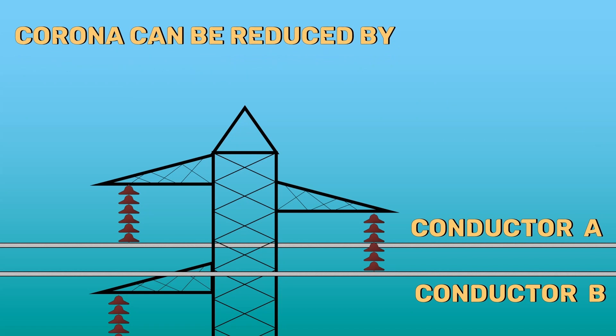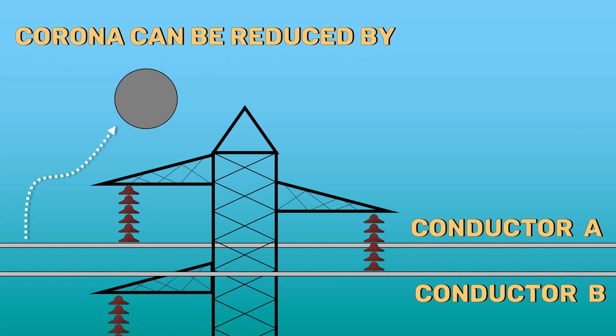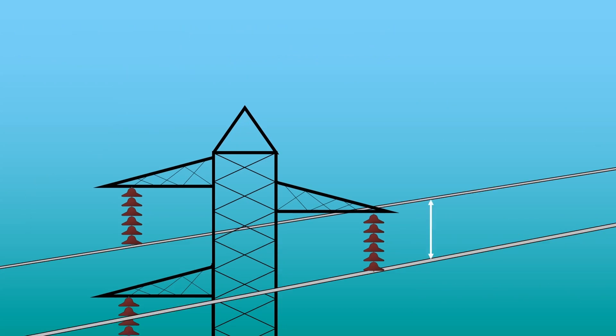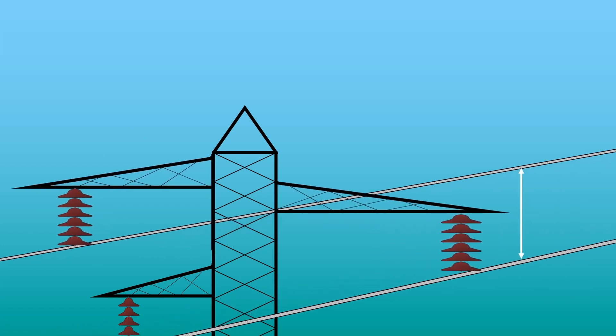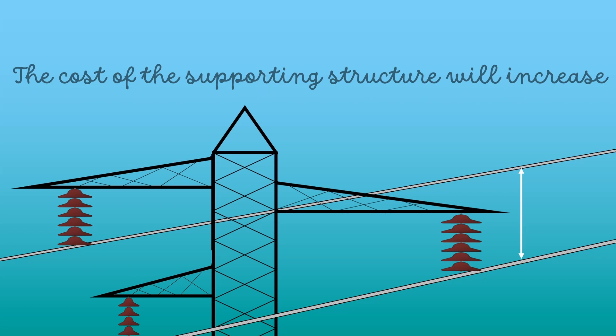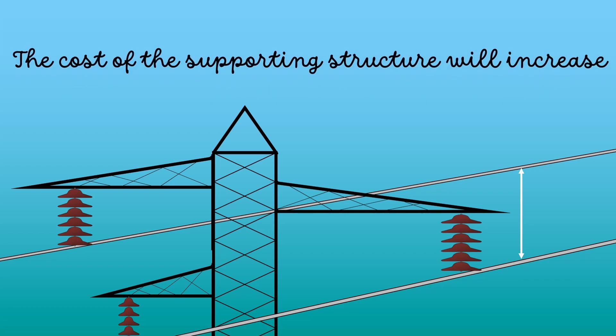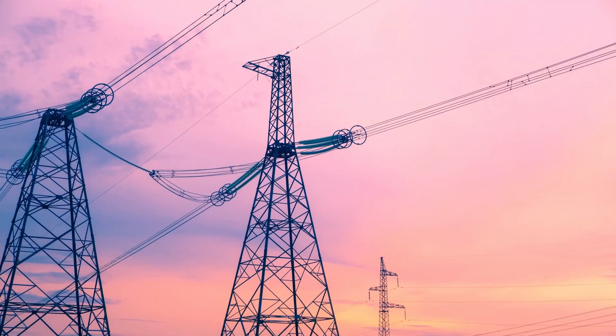The corona can be reduced by increasing the conductor's size and the conductor's spacing. However, the spacing cannot be increased too much otherwise the cost of the supporting structure will increase.